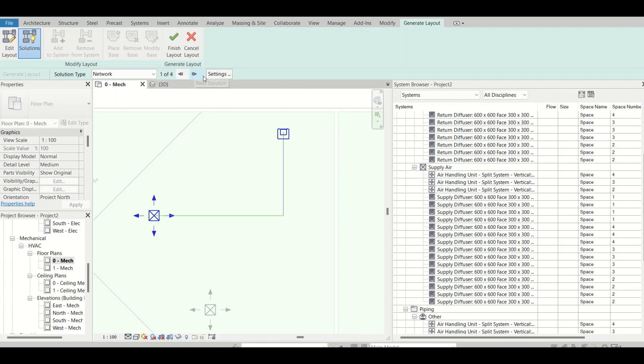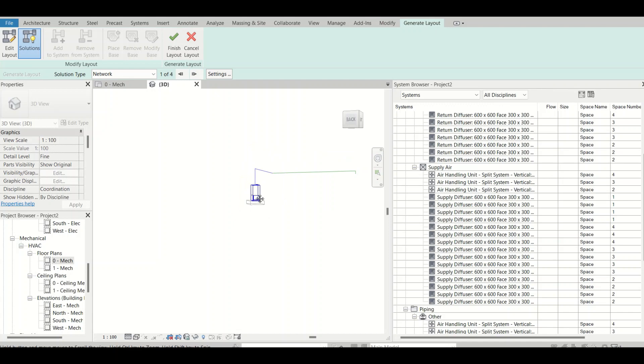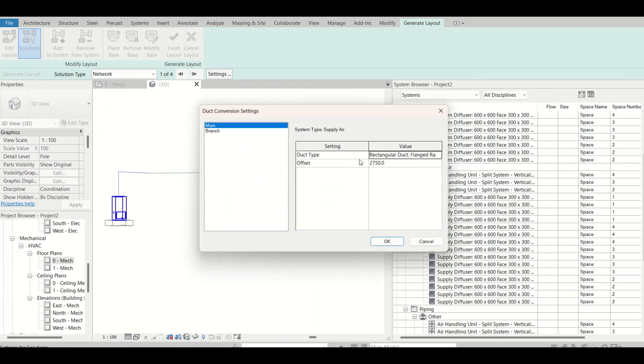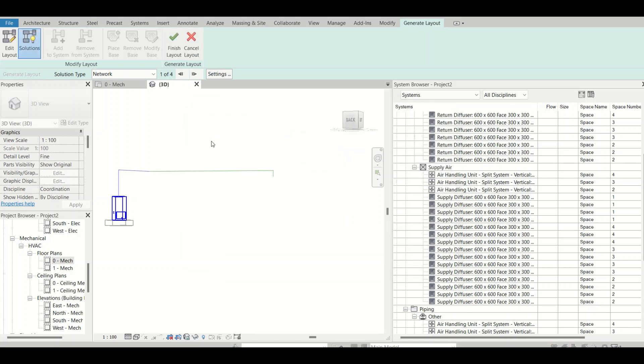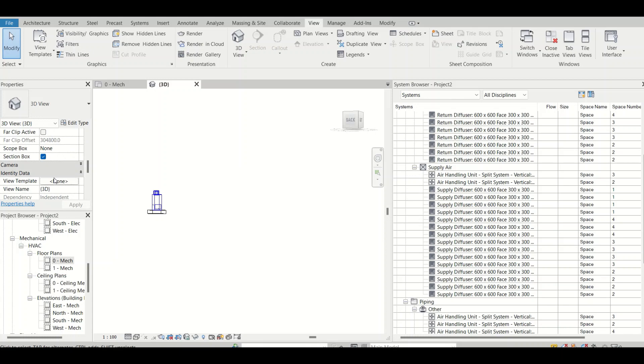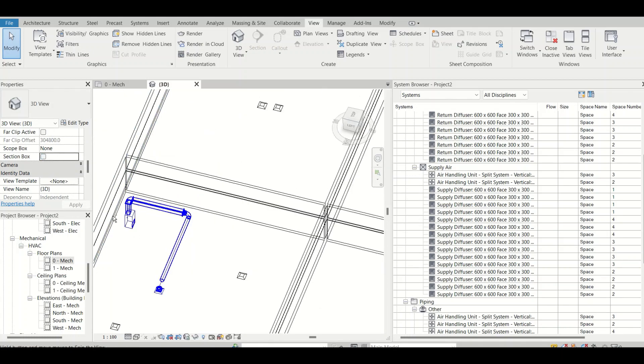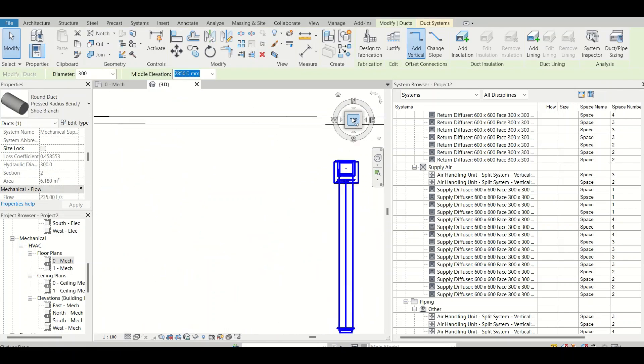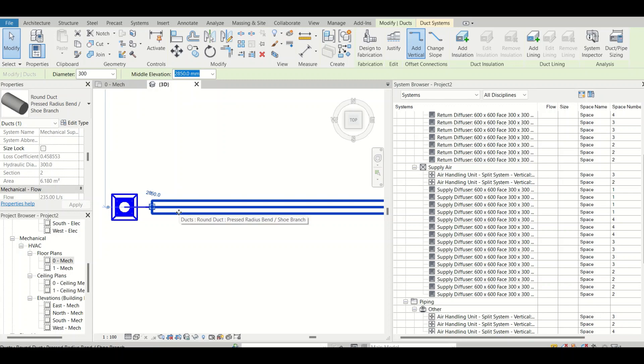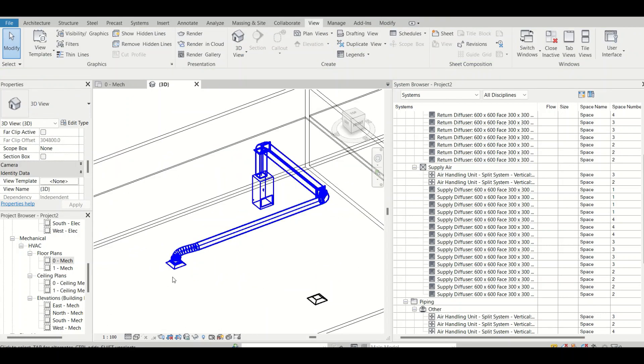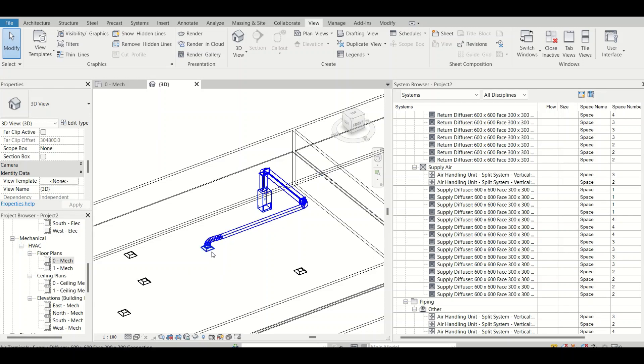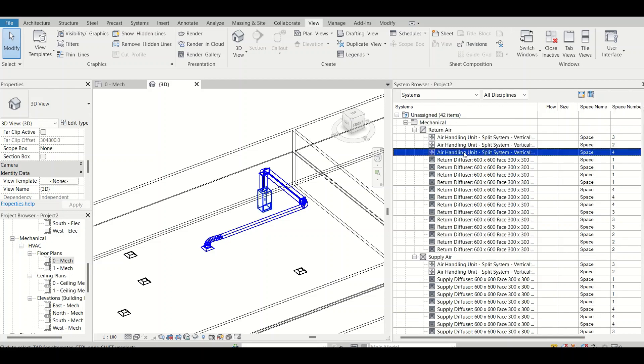I've already defined the system. I'll select the system, click Generate Layout, and there are multiple options as discussed in my previous video. I'll go to 3D view and set the main duct at 2750mm and branch at 2850mm. I removed the section box so the layout can generate. You can see the connection is made graphically. We've now properly connected this AHU and this air terminal. Our total was 44 unassigned elements — it should now be 42 since two elements are connected.